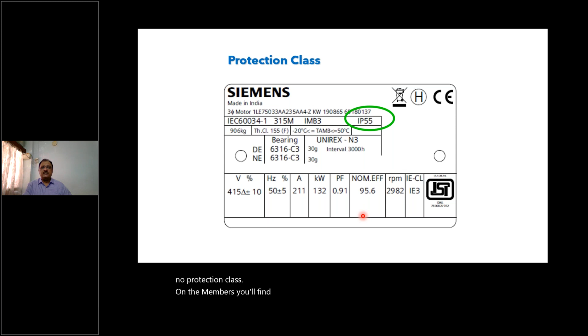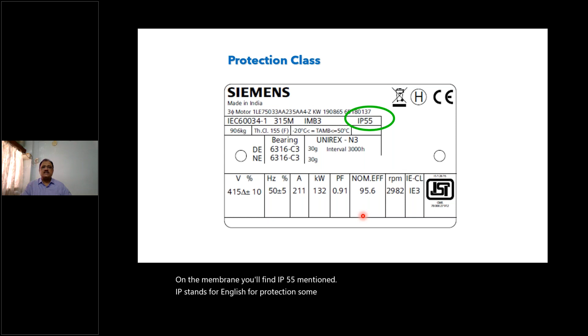Now, protection class. On the nameplate, you will find IP55 mentioned. IP stands for ingress of protection. Some people also call it international protection. What does this mean? The motor needs to be protected from external objects and water. So it is governed under IEC 60034-5, part 5 of the standard. Part 1 is for the general standard, part 5 is the standard for ingress protection.